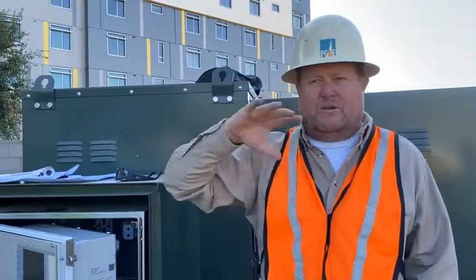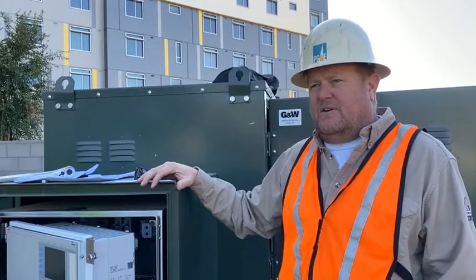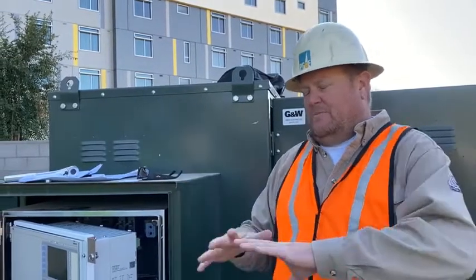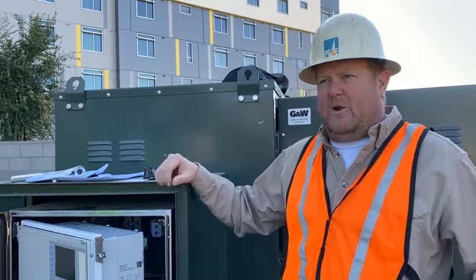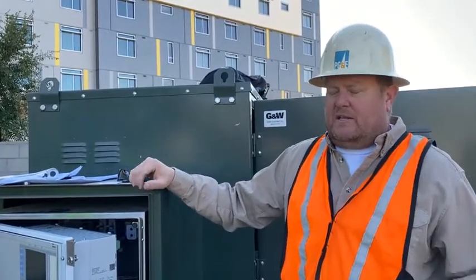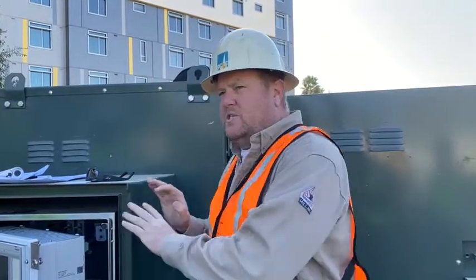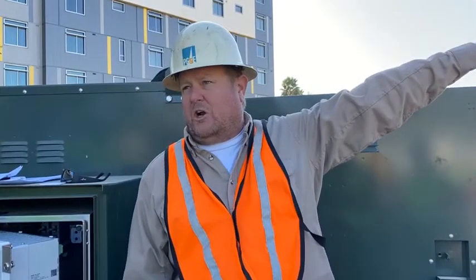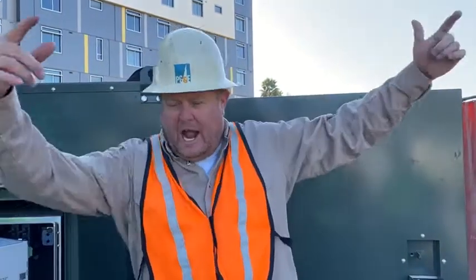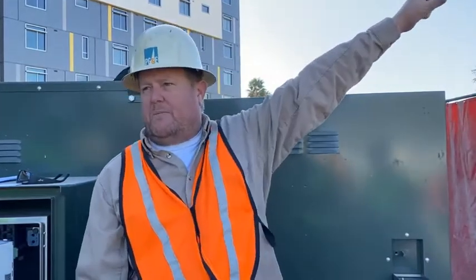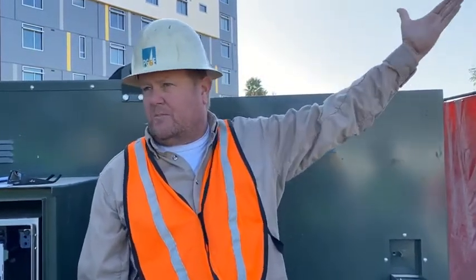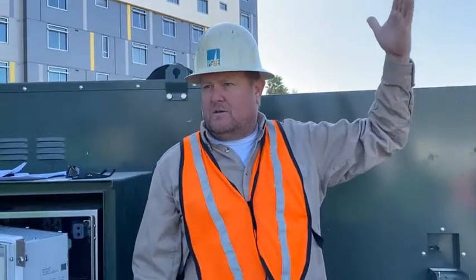And I'm sure your staff is going to be eventually working with him as he builds out that system and that controls. Because that system not only controls these switches, it's also going to control the main switchgear breakers. Because when you have a fault on that loop, that feeder breaker in your main switchgear is going to trip open. That's going to be your first issue, right?